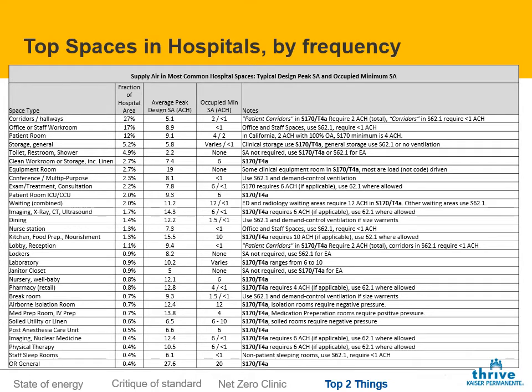So the number 10 through 1 spaces, I'll point out a few of those. ICU patient rooms, number 10, those actually have a different code requirement than normal patient rooms. But on average, our design engineers are designing those for 9 air changes. The code minimum is 6 air changes, which means you can easily do a 30% turn down.